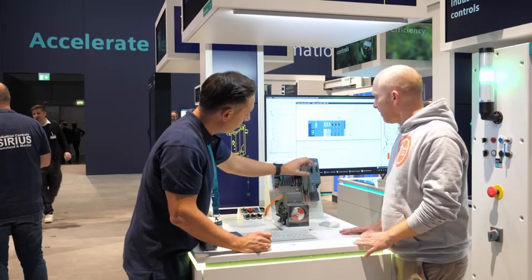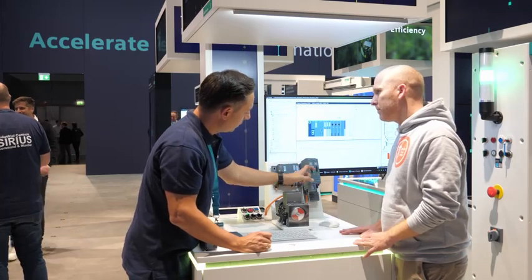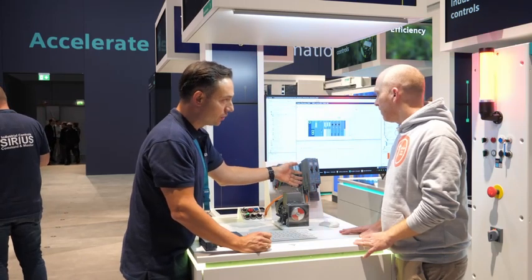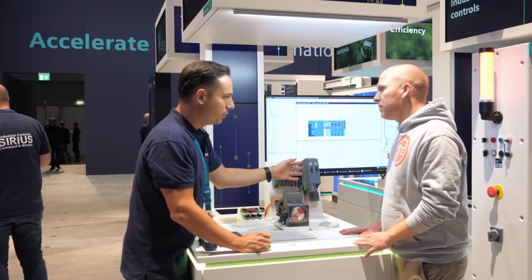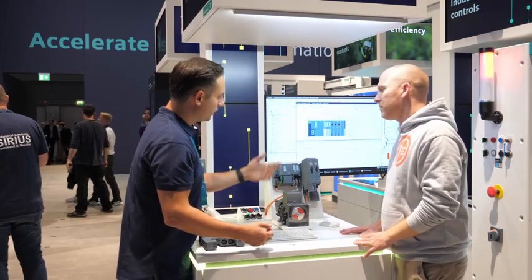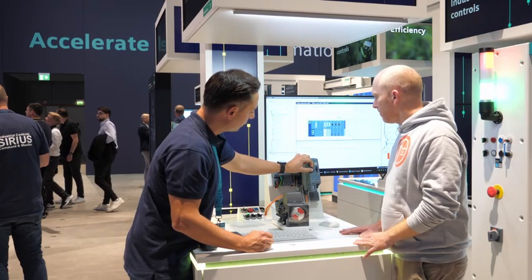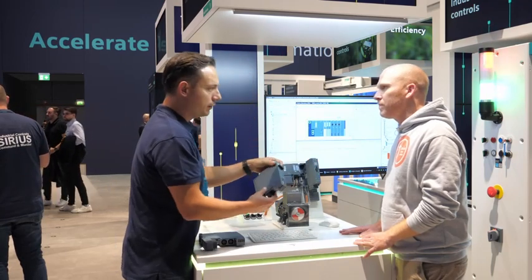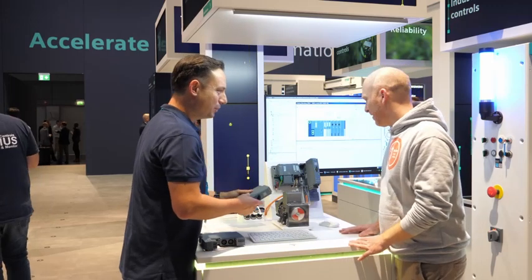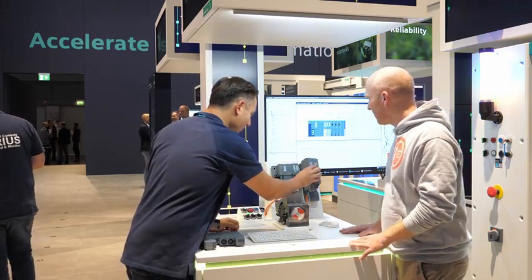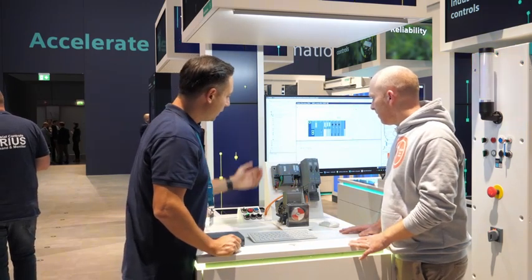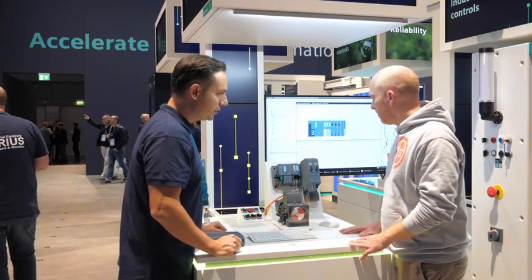So if you put a padlock here, then it cannot be turned on again. And here you have a mechanical disconnection as well. So that is very important to make sure that there is no voltage on the motor side. And the other alternative would be, of course, to take the complete device out, and then nobody can switch on. Quite a nice solution. And simply turn it back again, and the device is ready to go again.